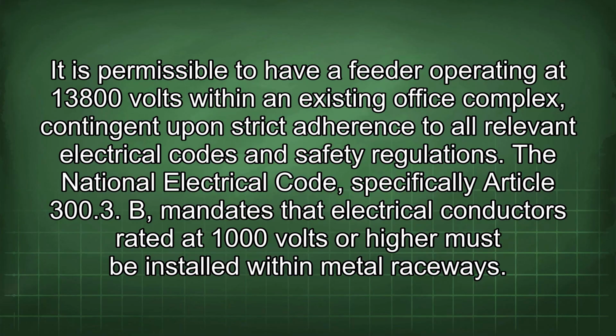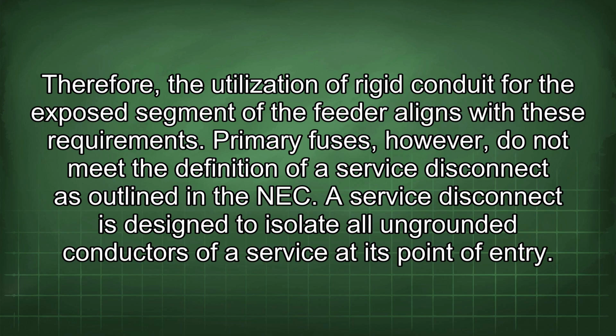It is permissible to have a feeder operating at 13,800 volts within an existing office complex, contingent upon strict adherence to all relevant electrical codes and safety regulations. The National Electrical Code, specifically Article 300.3(b), mandates that electrical conductors rated at 1000 volts or higher must be installed within metal raceways. Therefore, the utilization of rigid conduit for the exposed segment of the feeder aligns with these requirements.